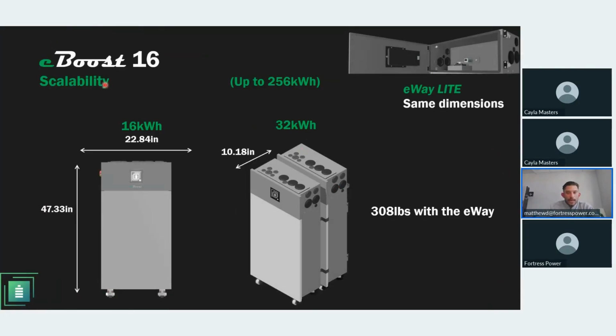It is scalable, like I said, up to 256, so that's 16 in parallel. It measures about 22.84 inches wide, 47.33 inches tall, and 10.18 deep. If you consider our previous solution, which was the eVolt Max, 2 of these is almost the same form factor as the eVolt Max, but you have double the capacity: 32 kilowatt hours versus 18.6. Each module will weigh about 308 pounds, including the E-way. So it is doable. It is manageable for sure.